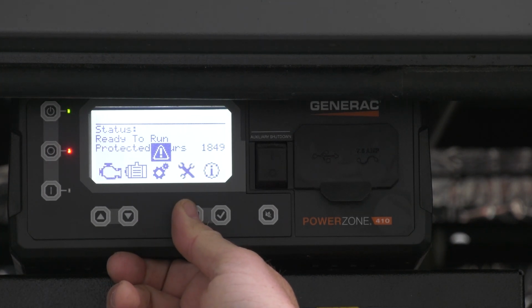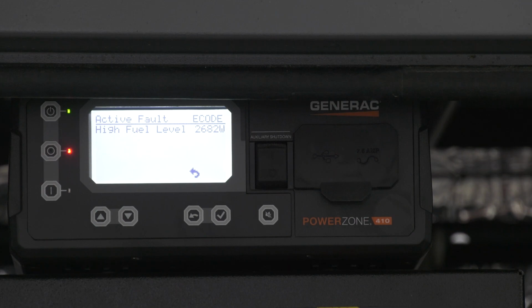So in a situation where you need the generator in an absolute emergency, if it's in low coolant level, obviously check it. If it's low, put it in there, clear your alarm, it'll be fine. If it's full of coolant and it says low coolant level, you've got a problem. That's something we have to fix.